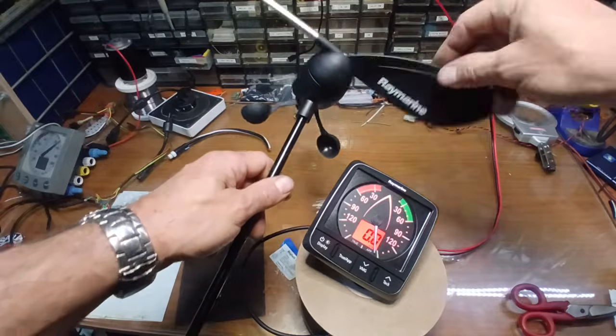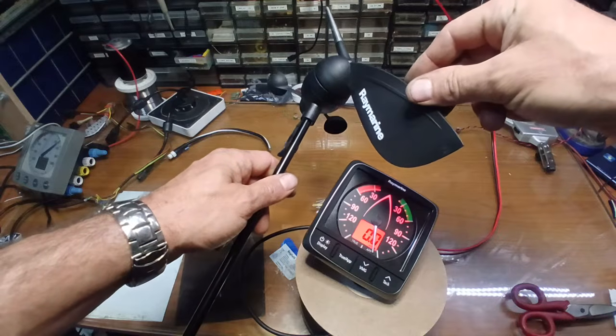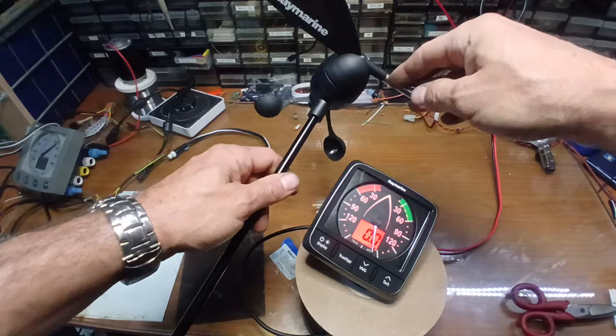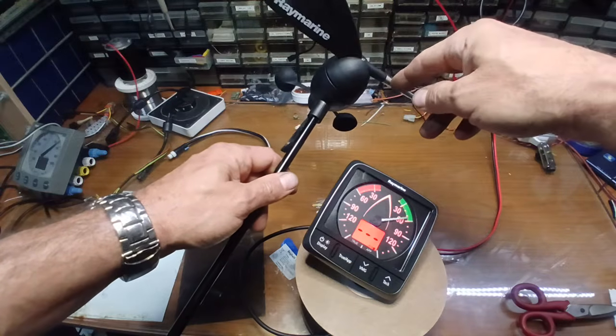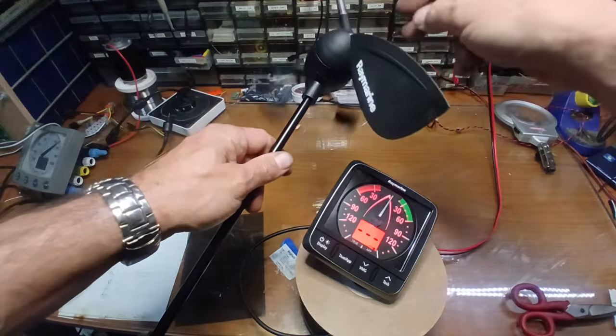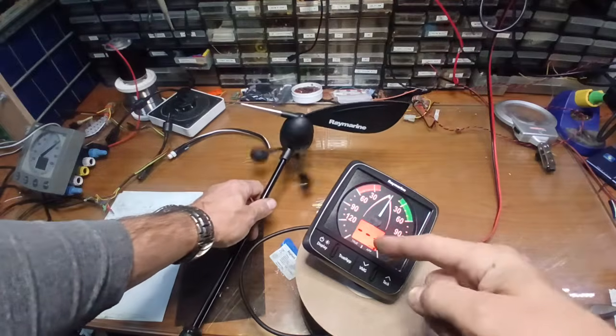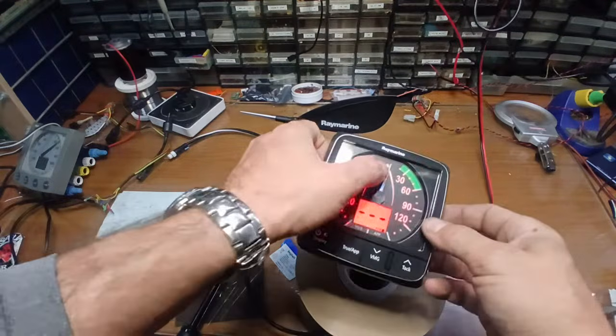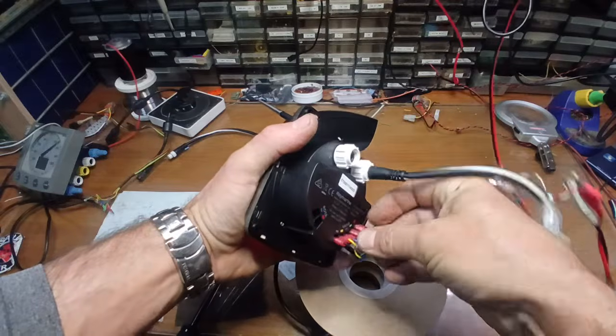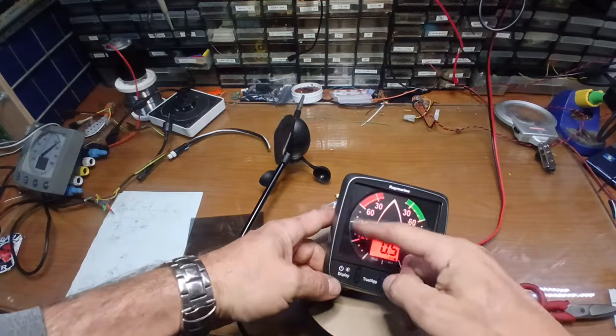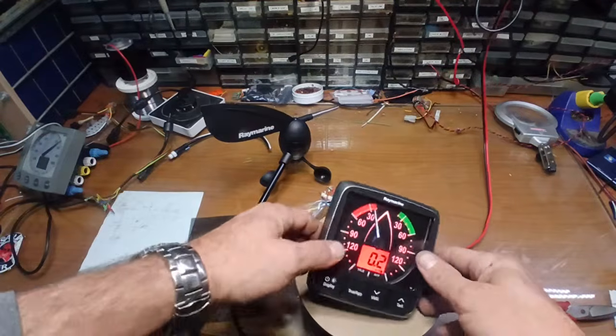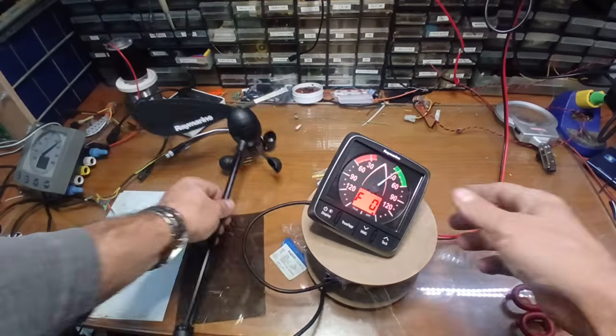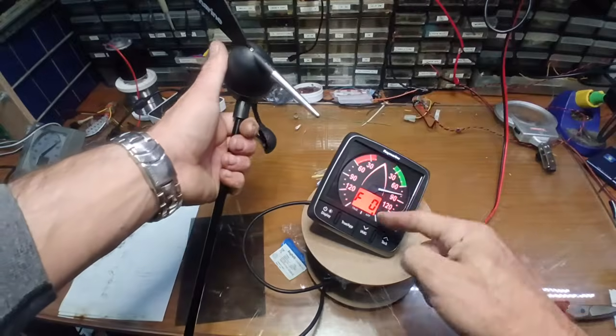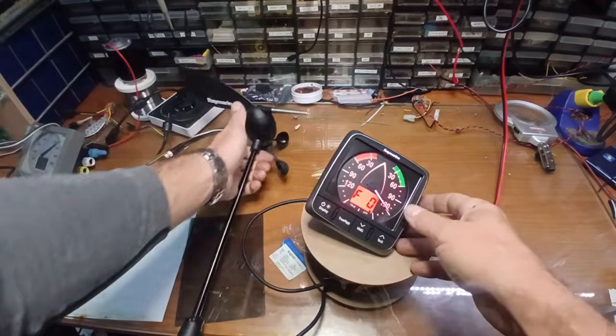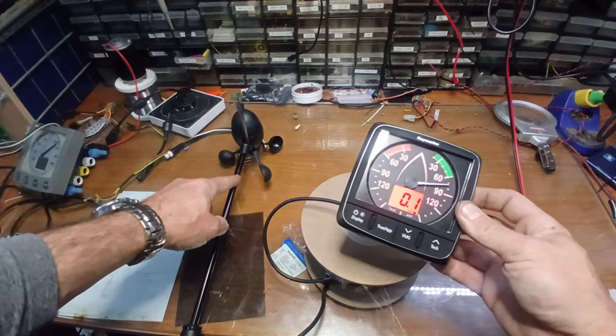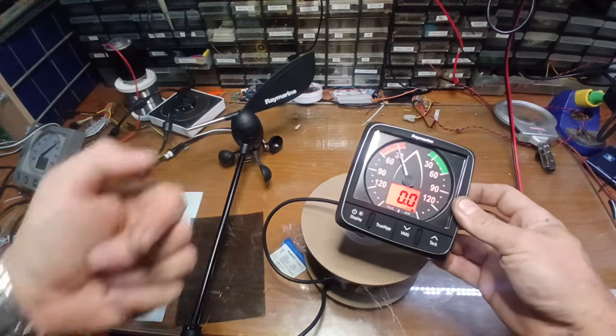A lot of people are asking: the instrument is working but it's showing like 180 degrees, or it's not measuring well. It will show something. Right now, in this moment, it complained, it went to the top and is not giving you anything at all. But a lot of times it will keep working, just not give you the proper direction, and will only stay on half of the quadrant.